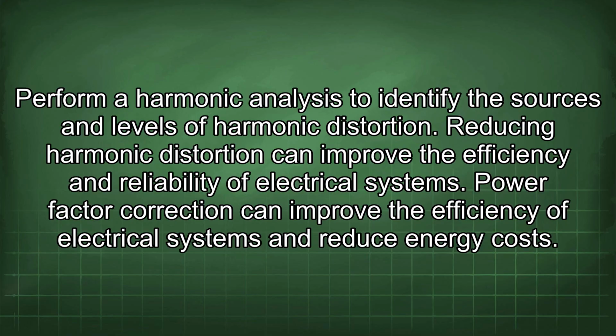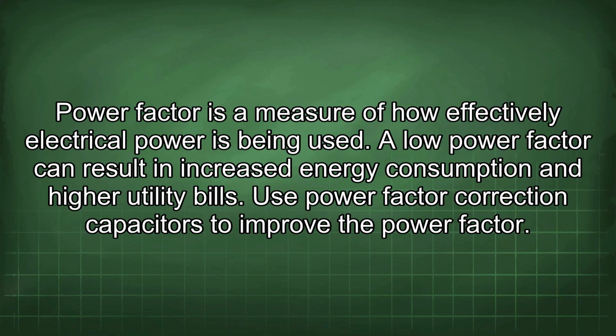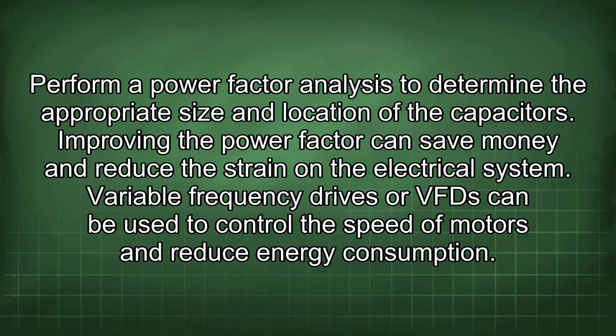Power factor correction can improve the efficiency of electrical systems and reduce energy costs. Power factor is a measure of how effectively electrical power is being used. A low power factor can result in increased energy consumption and higher utility bills. Use power factor correction capacitors to improve the power factor. Perform a power factor analysis to determine the appropriate size and location of the capacitors. Improving the power factor can save money and reduce the strain on the electrical system.